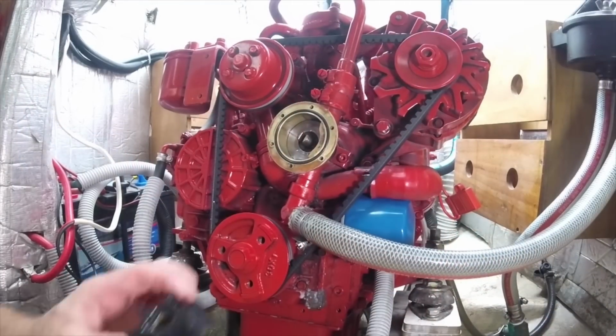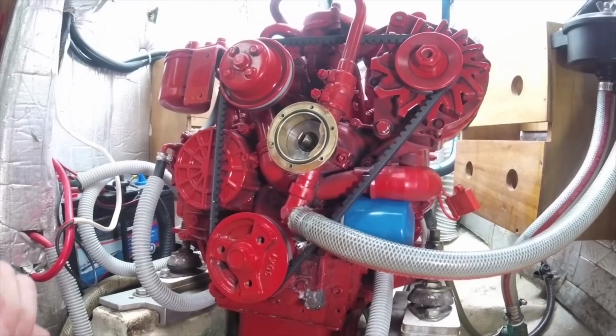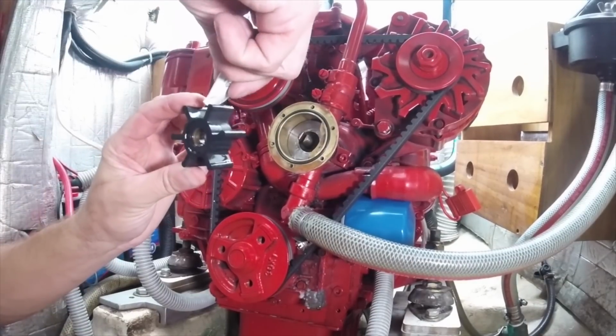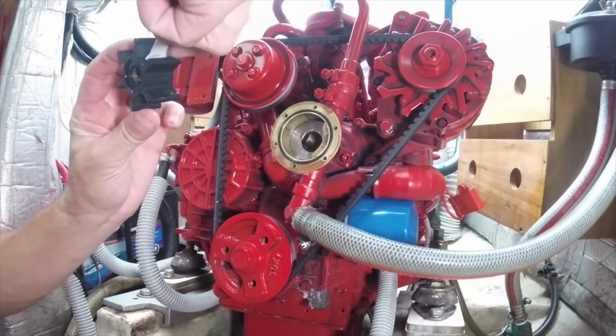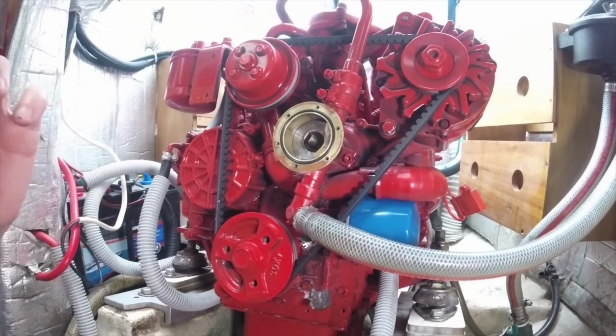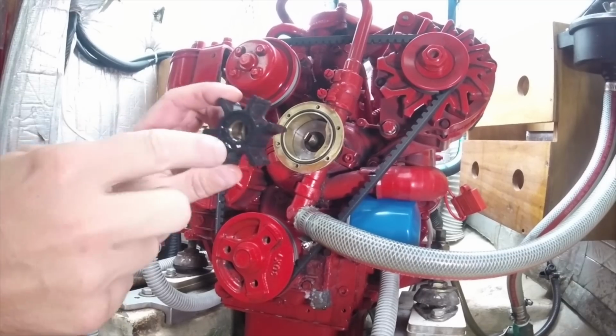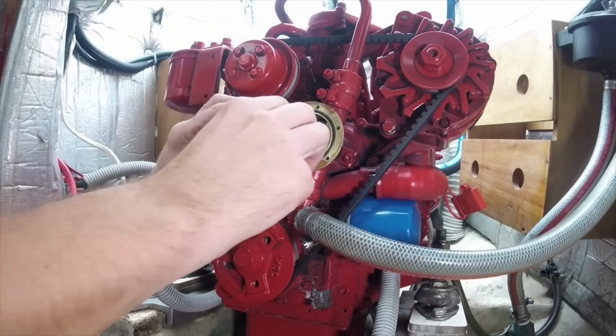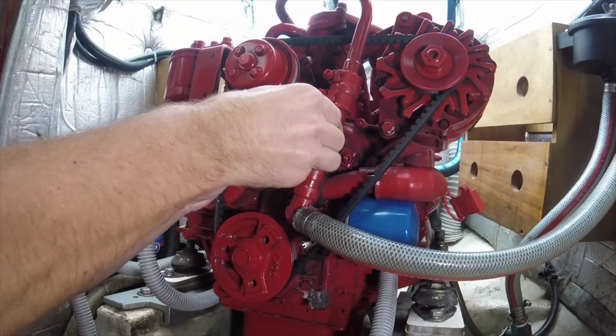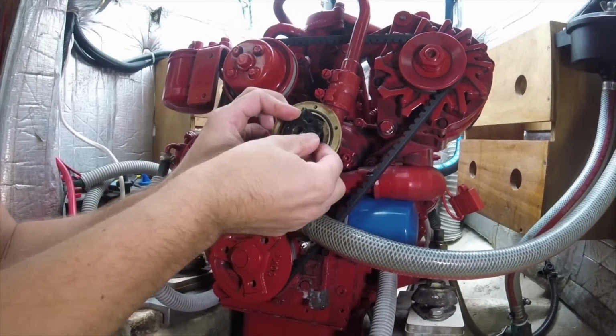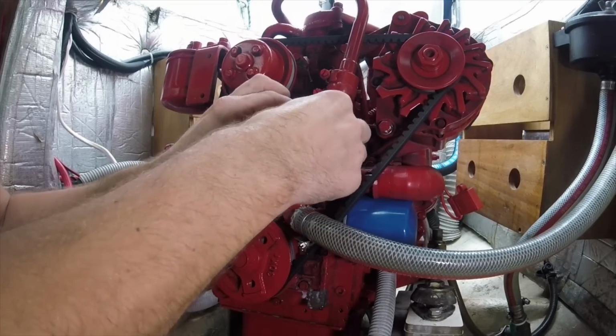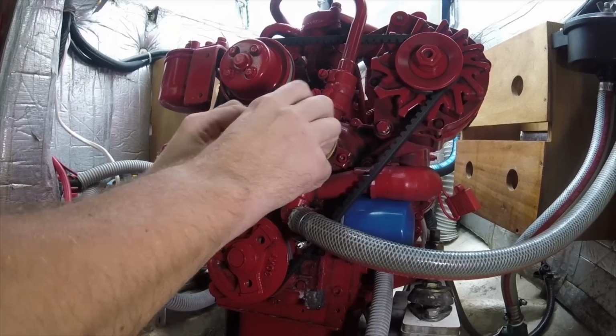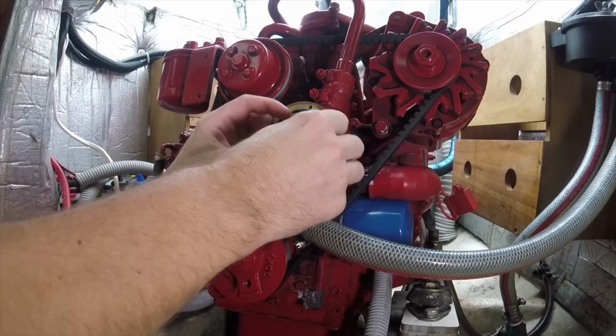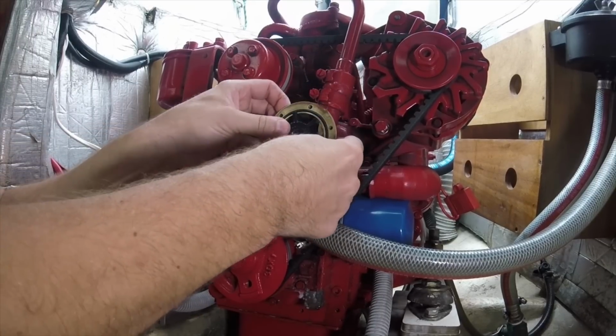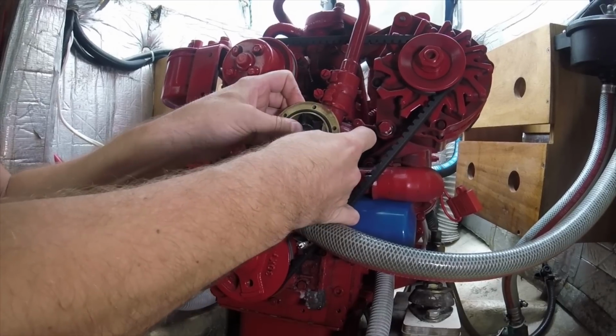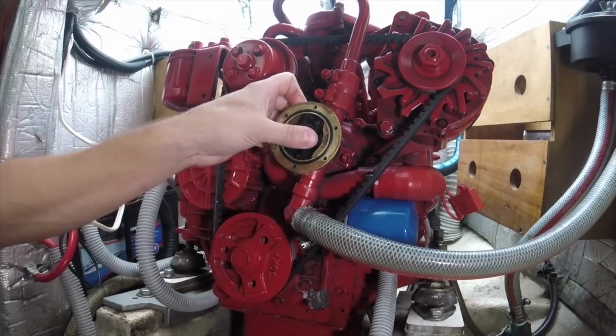The next thing we need to do is install the impeller, applying some lubricant that comes in the pack to the blades. Some people say to use an O-ring to compress the blades, but I find that if we just feed the impeller into the pump, twisting it in the direction the pump will turn, it'll gradually feed its way in and drop onto the spline.